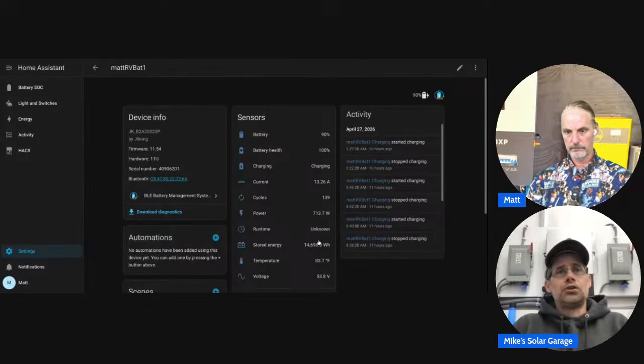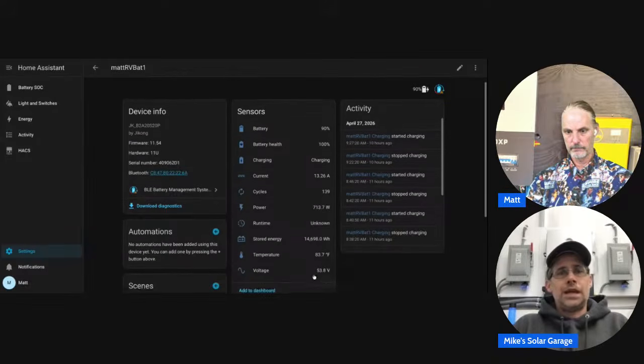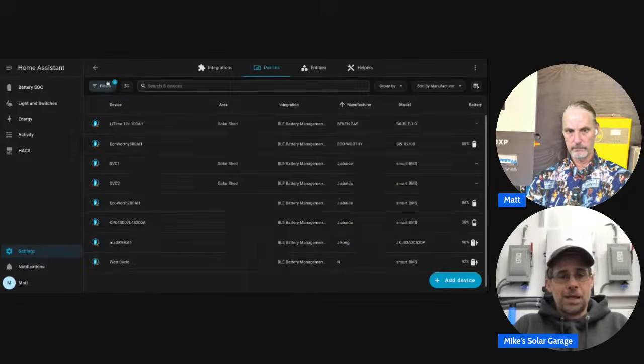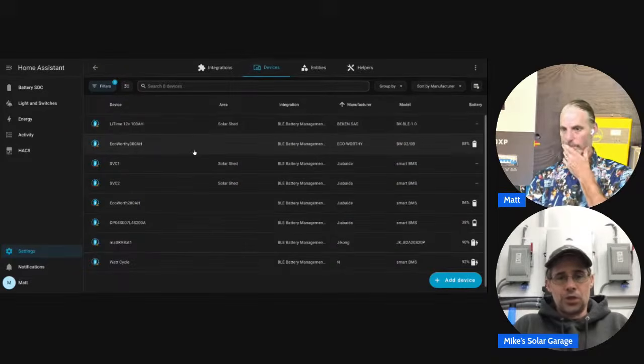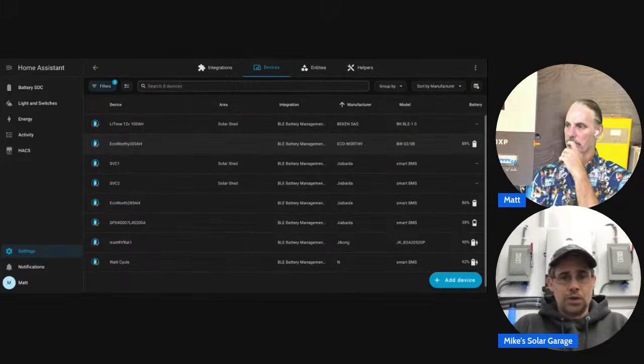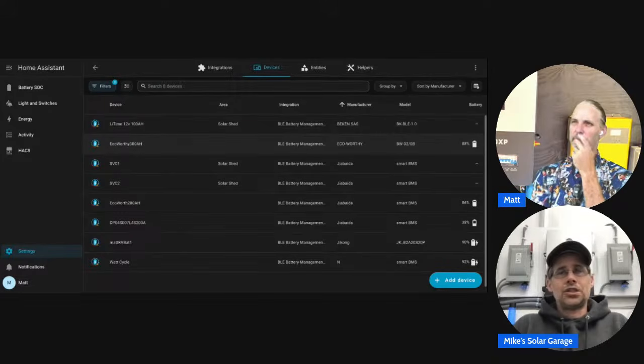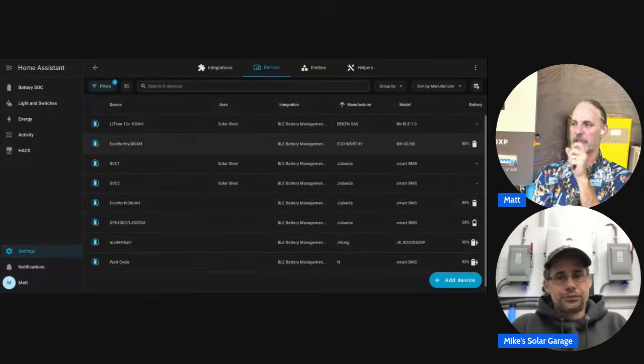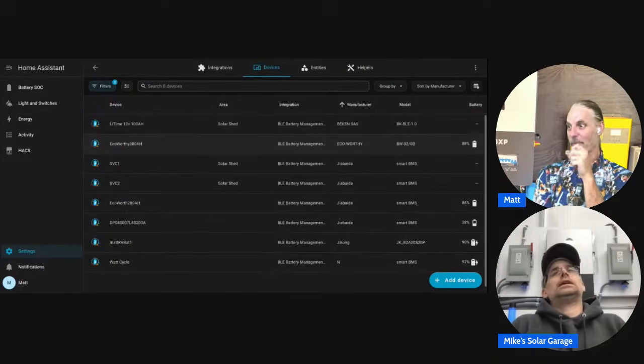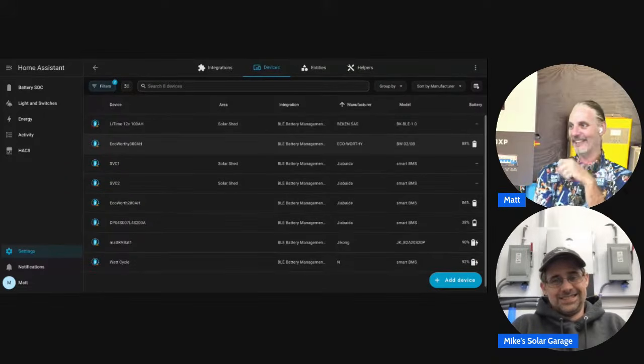The other thing too is your charge voltage, have a conservative level. Like I have mine at 56 for the charge, and then the float is 54. I had mine set at 56.2 and 54, so I'm really close to you. Occasionally I'll bump it to 56.6, but that's only because the EG4 batteries reset their state of charge at 56.6. So if you have EG4 batteries and you want them all to hit 100%, set it to 56.6, let it hit 56.6, and you'll see them all switch to 100%.